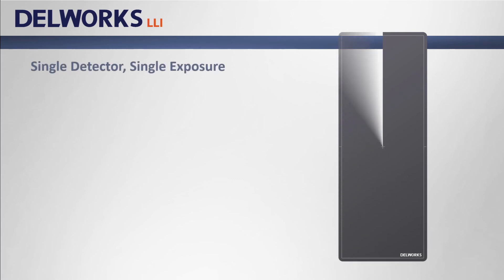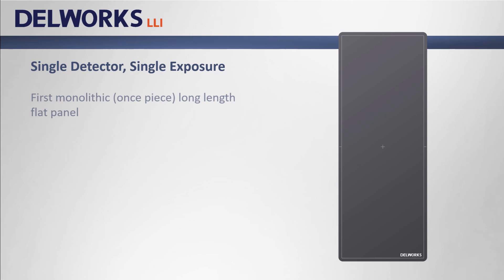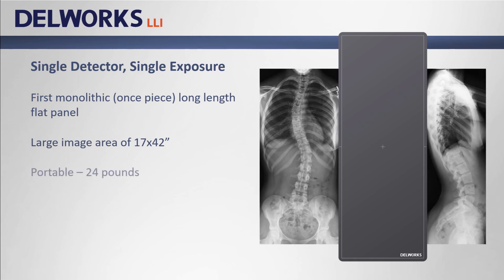This brings me to the ultimate long length imaging solution: Delworks LLI. Delworks LLI is the world's first monolithic long length flat panel detector — that means it's one single detector. Delworks LLI has a large image area of 17 by 42 inches. It's portable at just 24 pounds, so it can be used both upright or tabletop, and image data transfer is possible both wired or wireless.